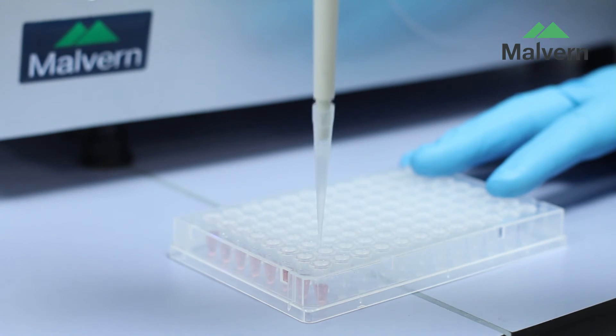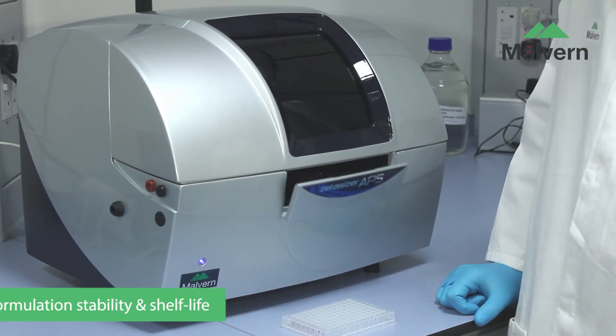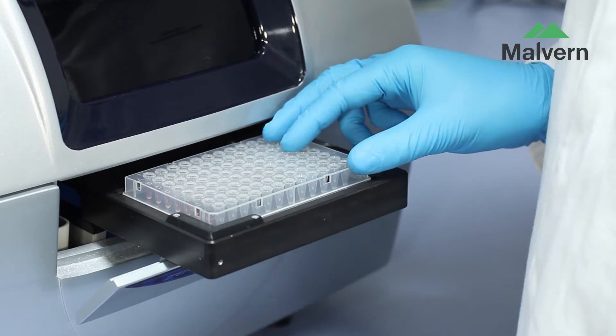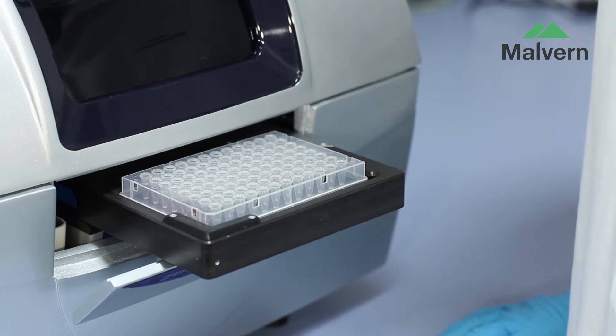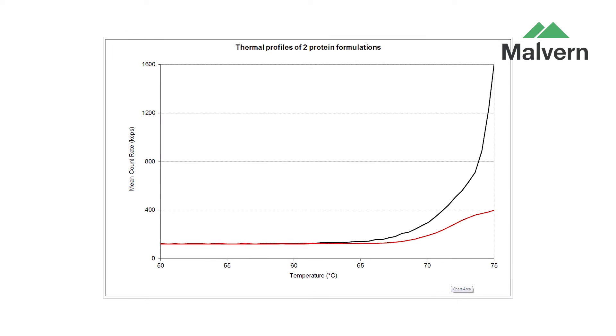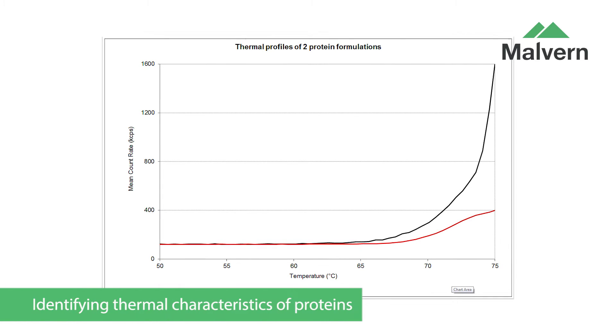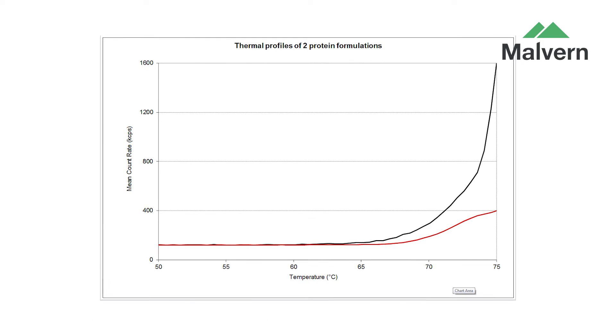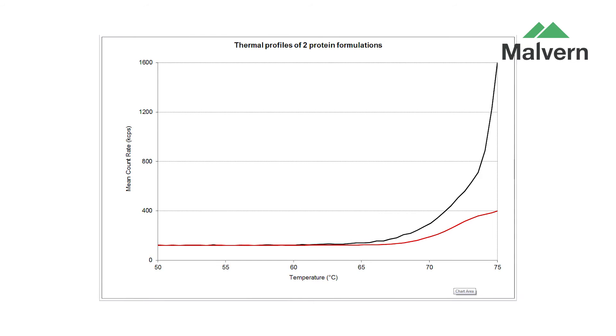The Zetasizer APS can monitor changes in size, scattering intensity and polydispersity over time to optimize conditions for long-term formulation stability. Protein size and scattering intensity can be measured over a user-defined range of temperatures. Any changes in protein structure in response to temperature changes are clearly identified, giving information on purity and an indication of the aggregation point, or the temperature at which aggregation begins.